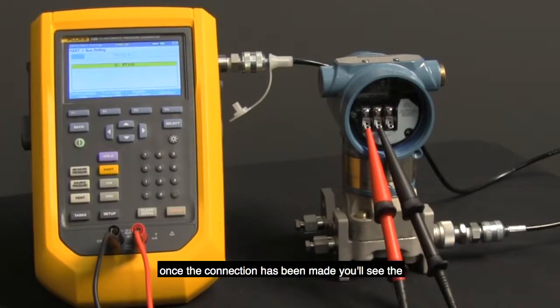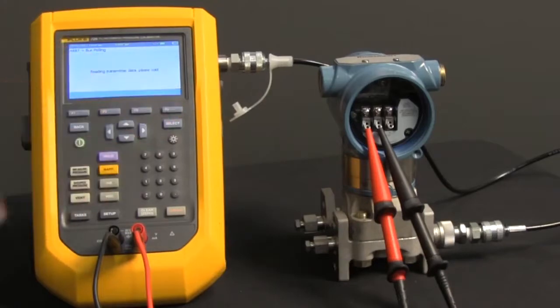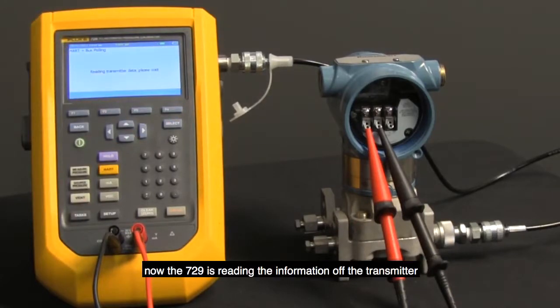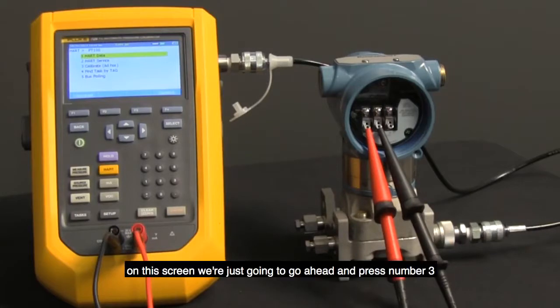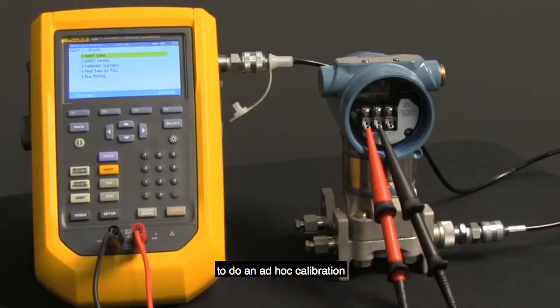Once the connection has been made, you'll see the device ID name and tag ID name of the device, and just press F4 to continue. Now the 729 is reading the information off the transmitter. On this screen, we're just going to go ahead and press number 3 to do an ad hoc calibration.